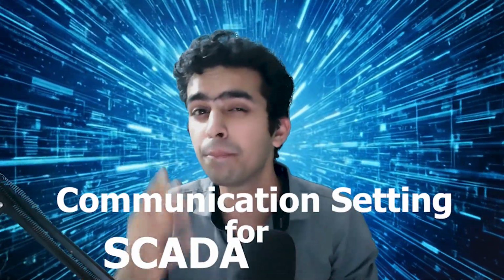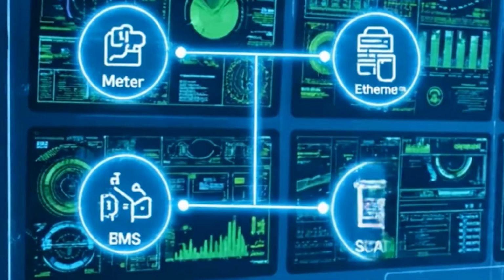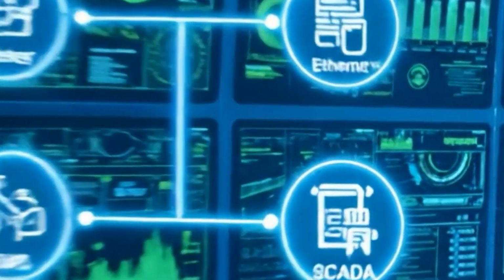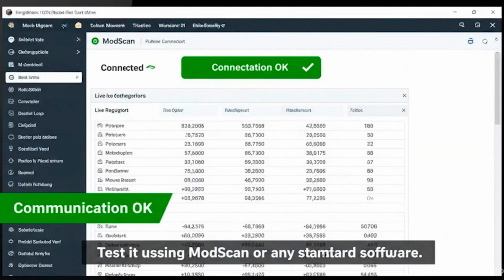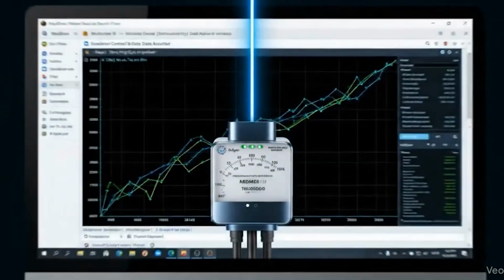And fourth one is the communication settings for SCADA or PMS integration. If you are connecting your dual source energy meter to a PMS, EMS, or SCADA system, make sure to test the Modbus address, baud rate, and parity correctly. Test it using Modbus scan or any standard software over RS485 or Ethernet, depending upon your system. So that's the complete overview of dual source energy meters, what they are, how they are used, why they matter, and how to practically buy and install them like a pro.